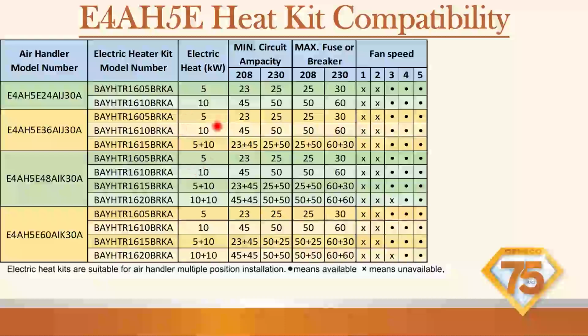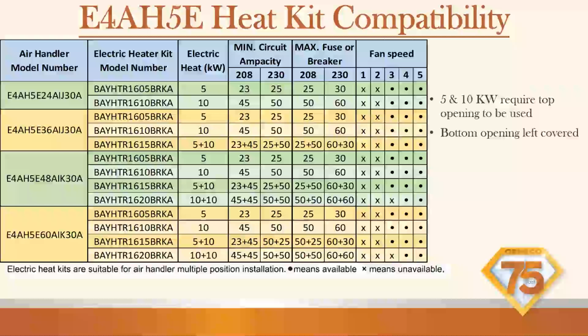Of course, the rating nameplate: for the 2-ton you've got a 5 and a 10, and 5, 10, and 15 for the 3-ton. And we can get up to 20 kW for the 4 and the 5. So that's going to tell you what your circuit breakers are for 230. You've got 2 60 amp circuit breakers in there. And then recommended fan speed settings. The 5 and 10 kW require the top opening to be used. I'll show you a picture of that in a second. Bottom opening left covered. So you've got 2 covers in there, and I'll show you. 15 kW and above must be dual circuit. I'll show you that in a second.